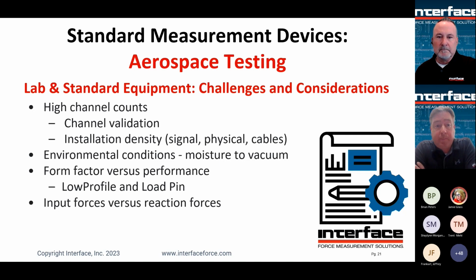Environmental conditions can widely vary here, depending on the type of test. Is the test outside, in which case moisture is a concern? Is it a vacuum test? Perhaps a thrust test at altitude. So different concerns there, but those are all things to consider. Moisture, for example: we can provide load cells with additional environmental protection. And there are some specific installation schemes that can be utilized to try to avoid moisture ingress to the load cell, making sure the connectors are oriented correctly would be one example, and some other things to consider there.